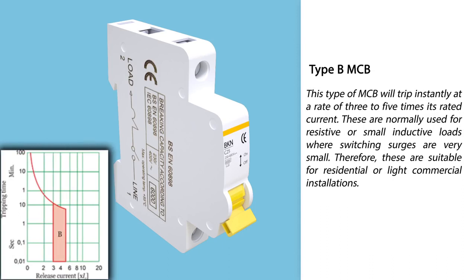Types of miniature circuit breakers: Miniature circuit breakers are classified into three major types according to their instantaneous tripping currents — Type B, Type C, and Type D. Type B will trip instantly at a rate of three to five times its rated current. These are normally used for resistive or small inductive loads where switching surges are very small, and are therefore suitable for residential or light commercial installations.